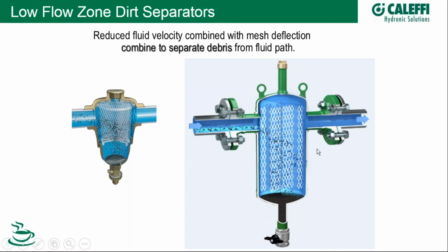so the fluid continues down through the system. As the separator does its job getting rid of debris, unlike the Y strainer, which starts to clog up, the debris gets dropped away from the flow path. So you don't have an increased pressure drop as it's doing its work. And they have a lot more volume, obviously, so it lengthens the interval times versus a Y strainer.